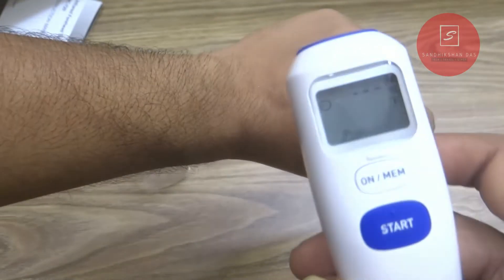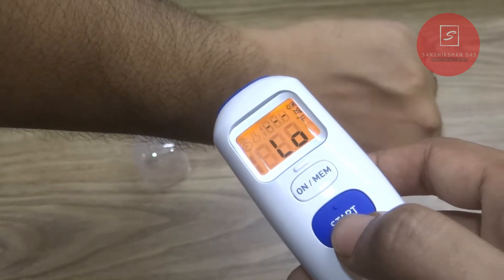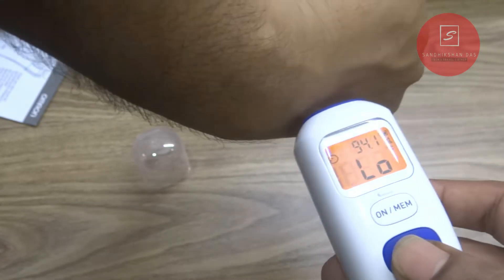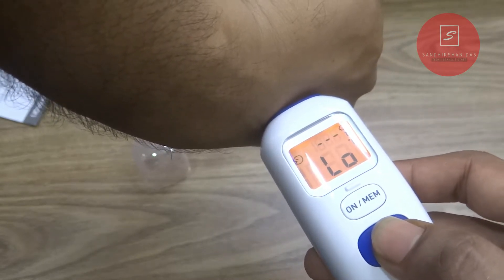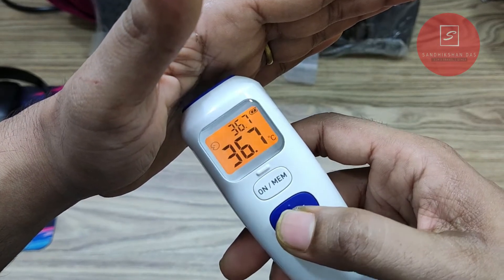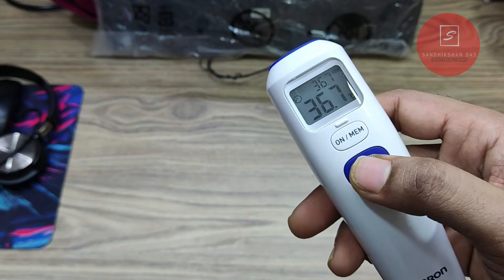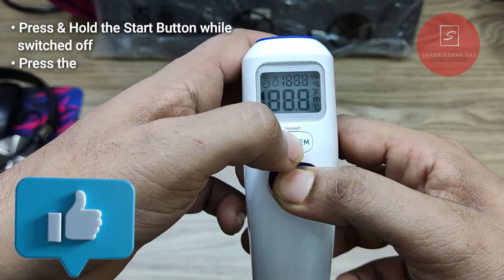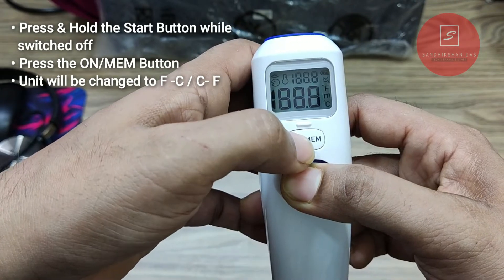That may give a low or high temperature error due to the unrealistic temperature of the body. If the body temperature is greater than 100 degrees Fahrenheit, it will give a HI message on the display. If the body temperature is below 93.2 degrees Fahrenheit, it will show LO, meaning low. When you measure the temperature for the second time, the first reading will show at the top right corner. You can also change the temperature unit from Fahrenheit to Celsius or vice versa by pressing and holding the start button and the on/MEM button simultaneously until the unit sign changes.